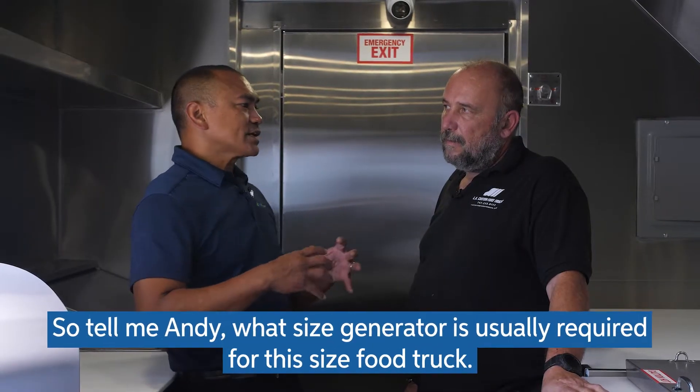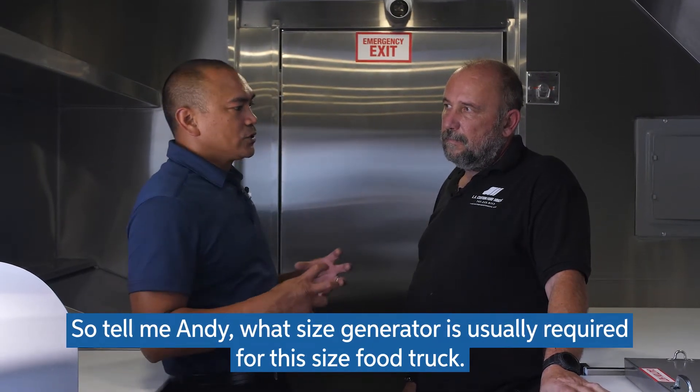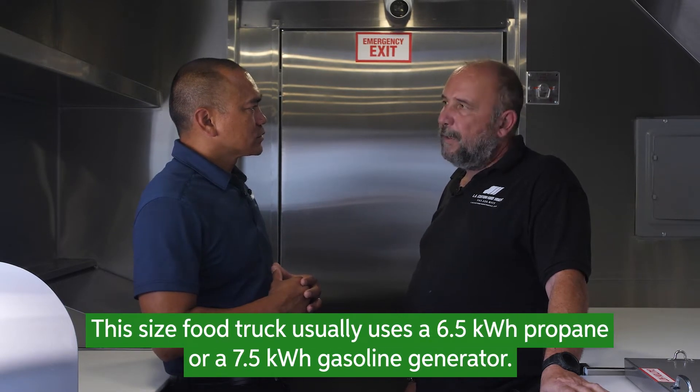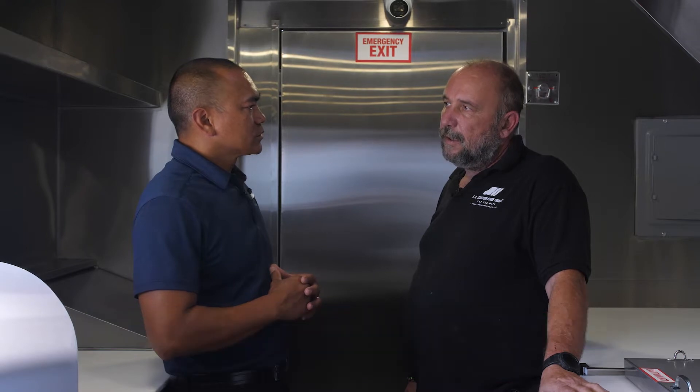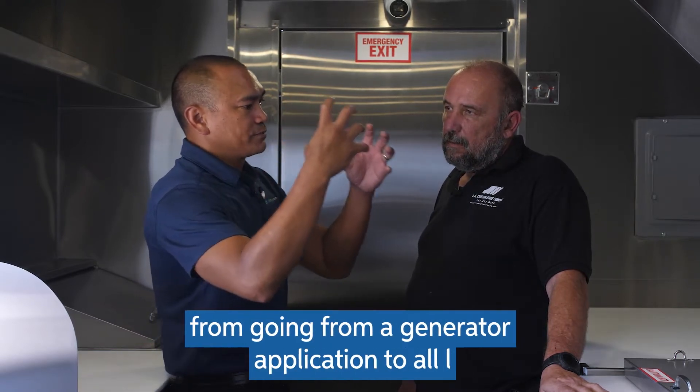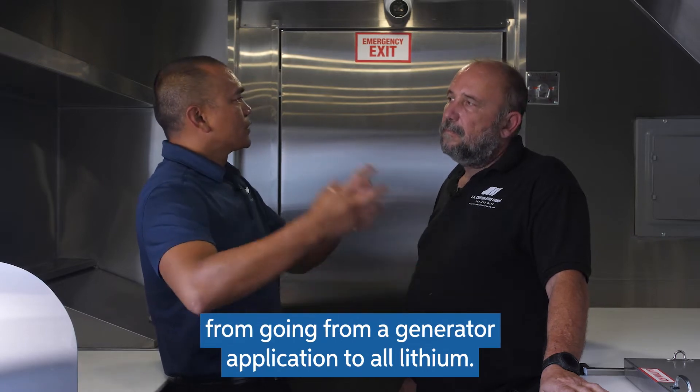So tell me, Andy, what size generator is usually required for this size food truck? This size of food truck, we usually use a 6.5 kilowatt propane or a 7.5 kilowatt gasoline generator. Okay, so can you tell me what the benefits are from going from a generator application to an all-lithium setup?